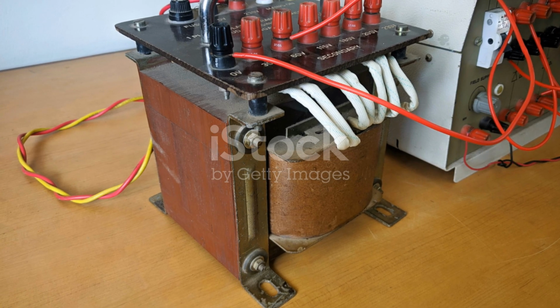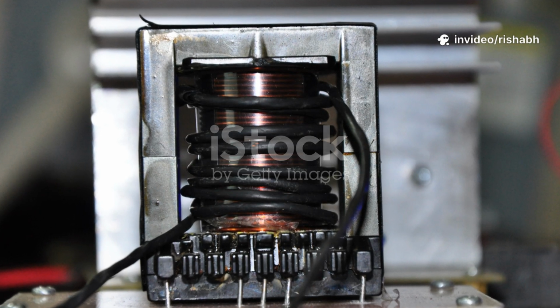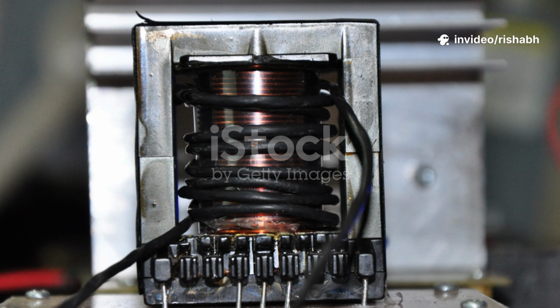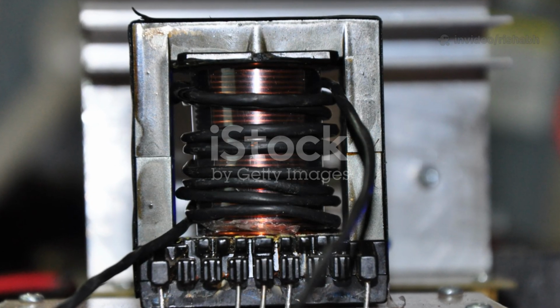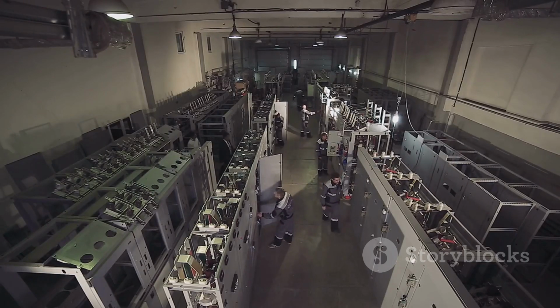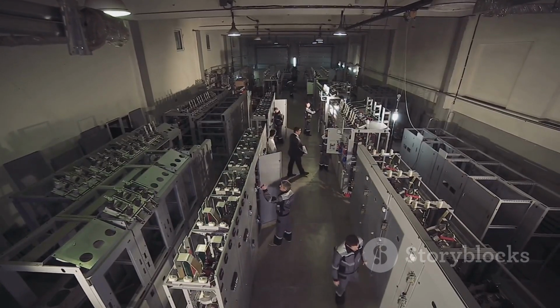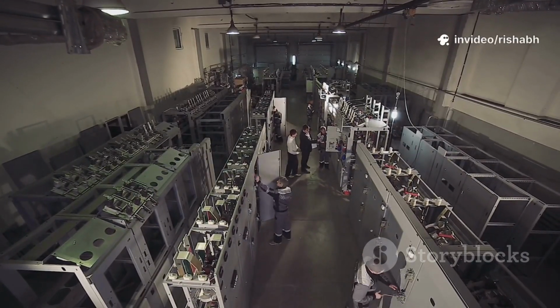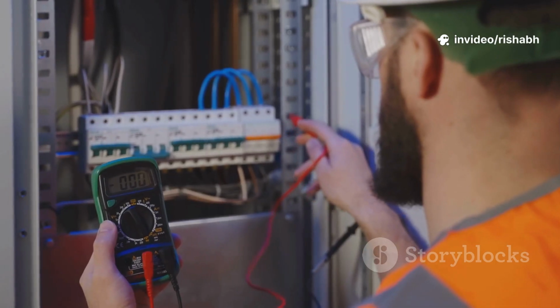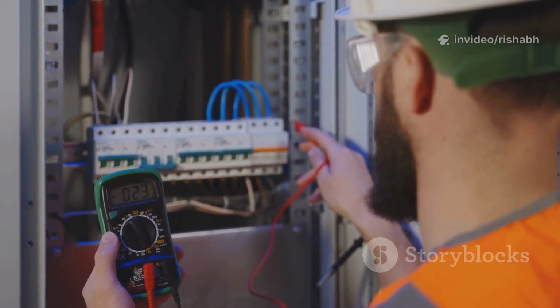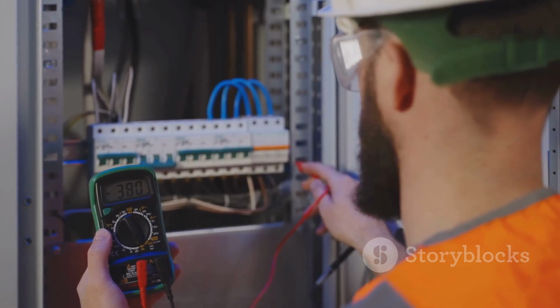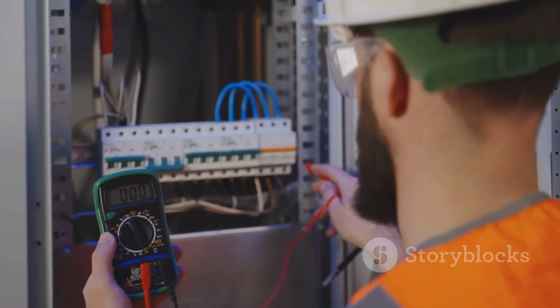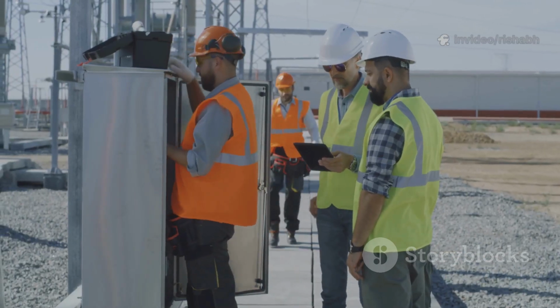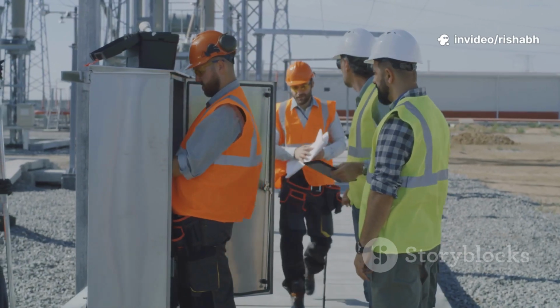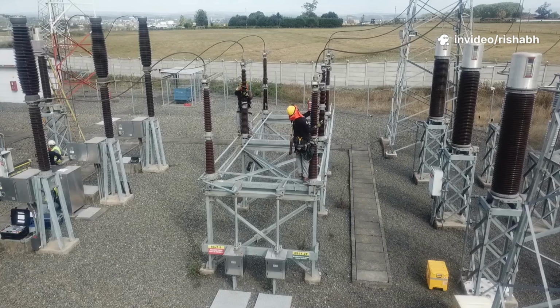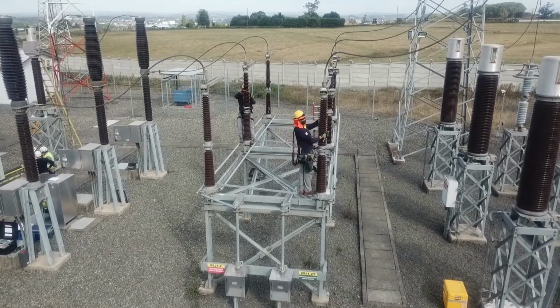Secondly, the delta winding on the high voltage side acts as a natural filter for third harmonic currents. These harmonics are generated by non-linear loads, like modern electronics, and can cause overheating and interference. The delta winding effectively traps these problematic currents, allowing them to circulate within its triangular connection without polluting the upstream high-voltage network. This harmonic suppression leads to better power quality and improved efficiency for the entire system. It's like having a built-in cleaning crew for your electrical supply.